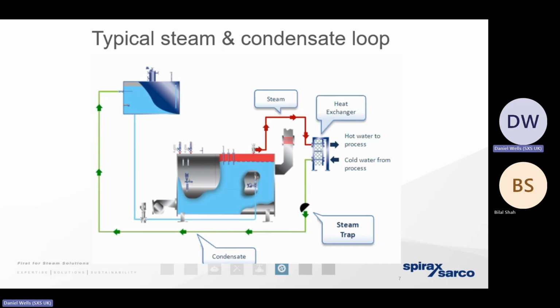So a steam trap's a passive device. We need a pressure drop across the steam trap. In other words, if we've got a pressure of 1 bar gauge within the heat exchanger, we need the pressure less than 1 bar gauge downstream, so the steam is capable of pushing the condensate away. So at this point, we should hopefully have a little bit of pressure within the condensate, and that's going to help the condensate move. Ideally, all the way back to the boiler house again, if not to some form of a reservoir where we can pump that condensate.